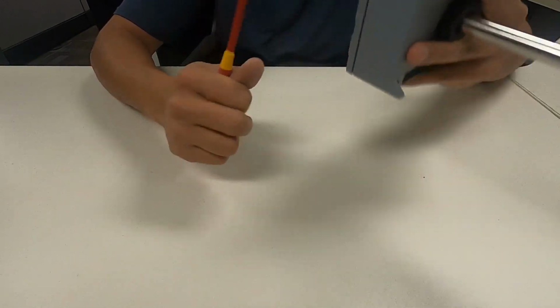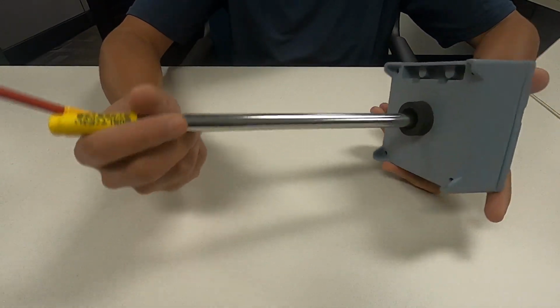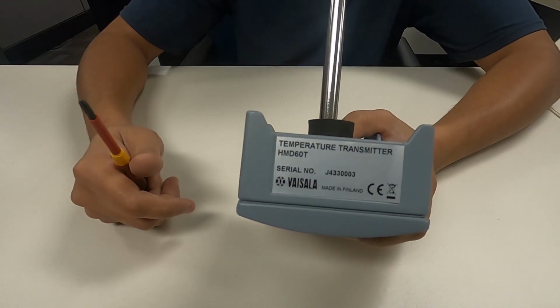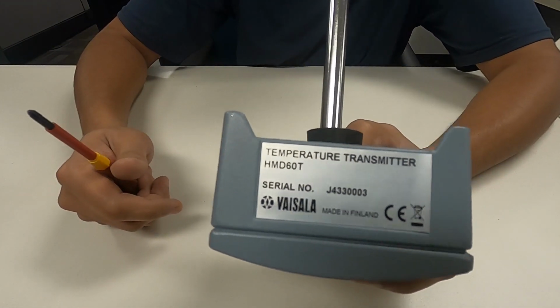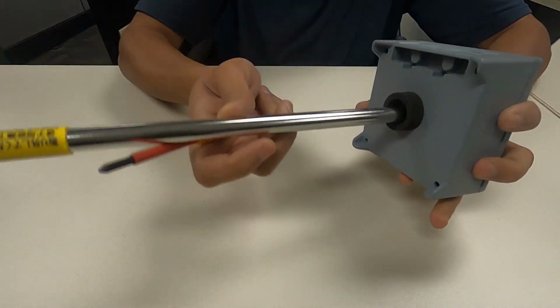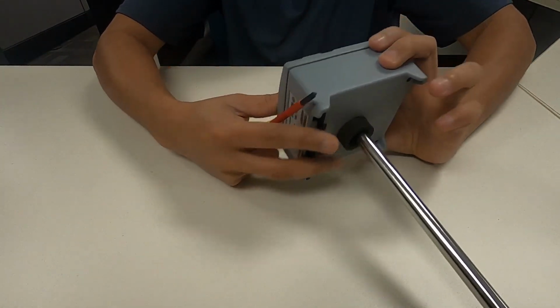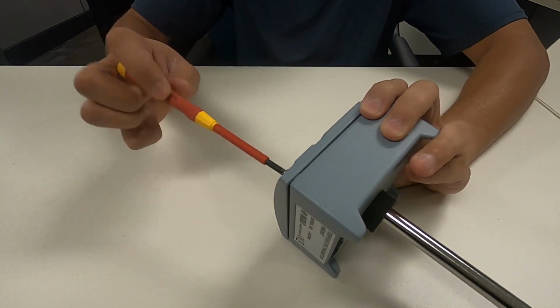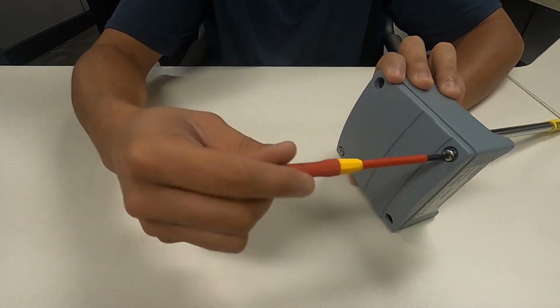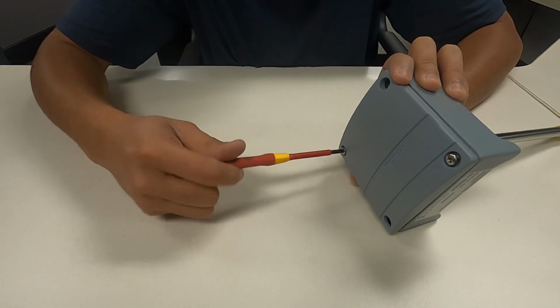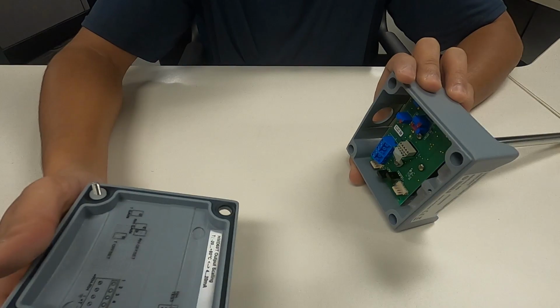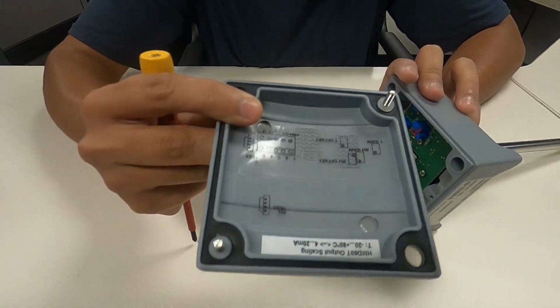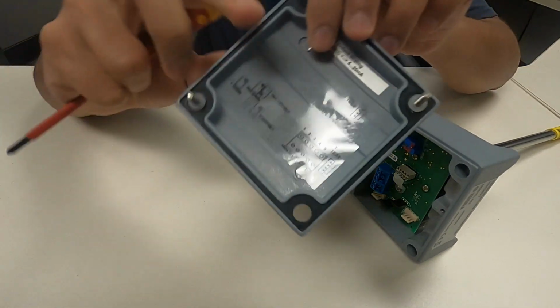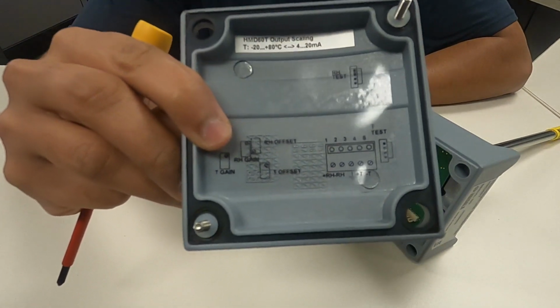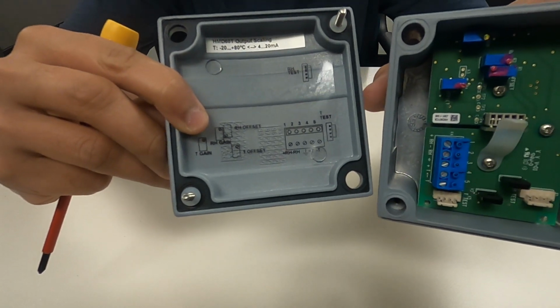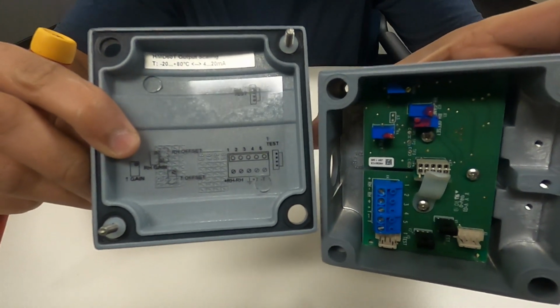So humidity plays a very important role in pharmaceuticals. If you are working in a pharmaceutical application, selecting a humidity sensor, then you might have to have the precision or the accuracy which is mentioned in their specification. Humidity sensors can give you an accuracy of plus or minus 2%, plus or minus 3%, and so on. So you might have to look closely into the specification: what the customer needs, what type of sensor he needs for the humidity, and what his precision has to be while selecting.